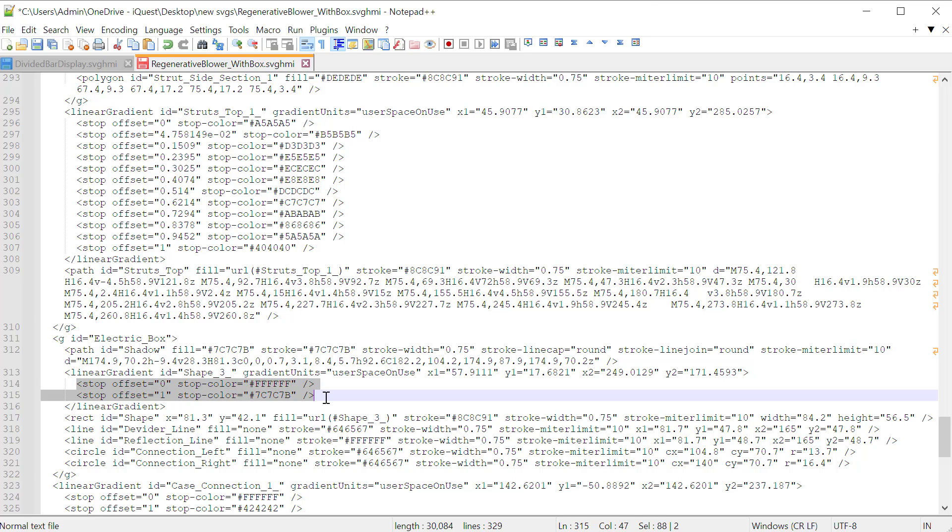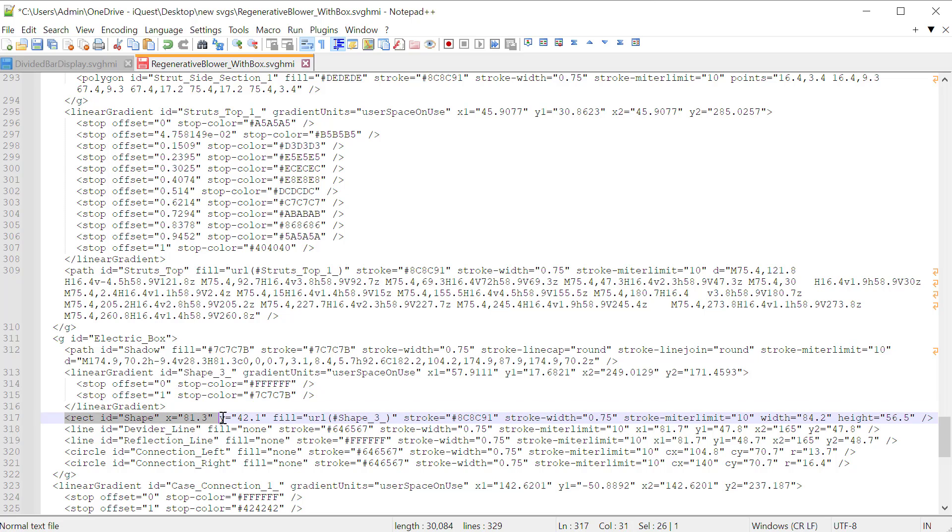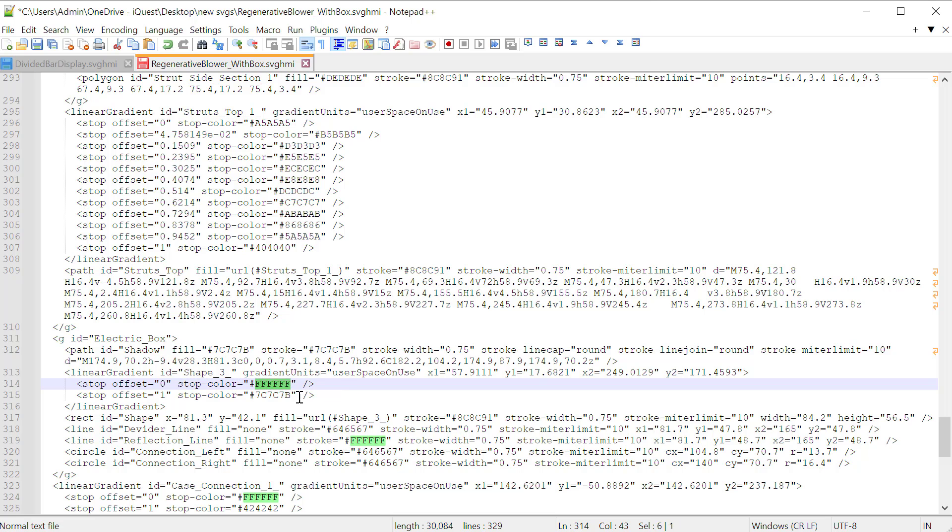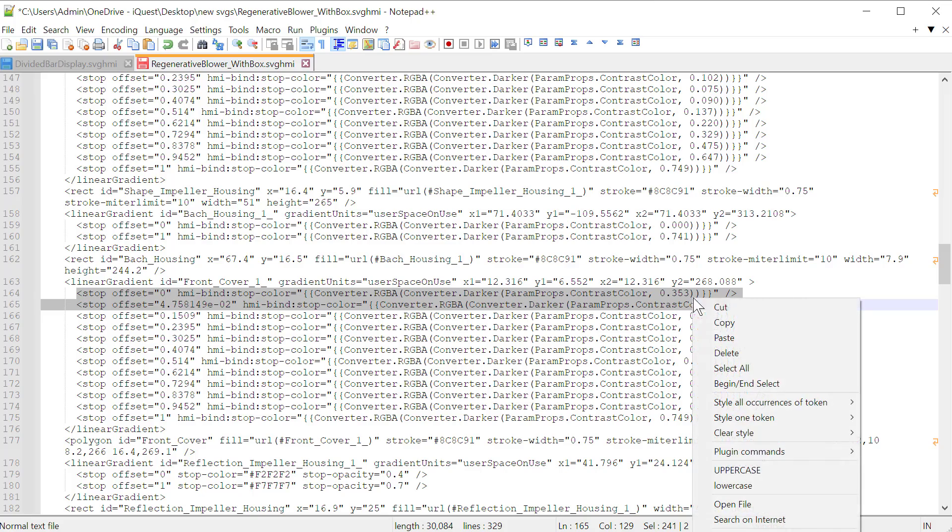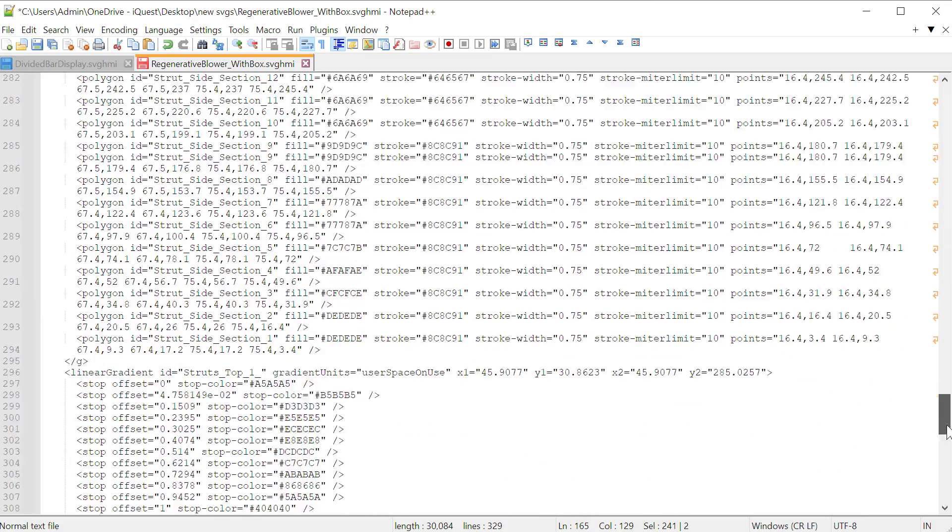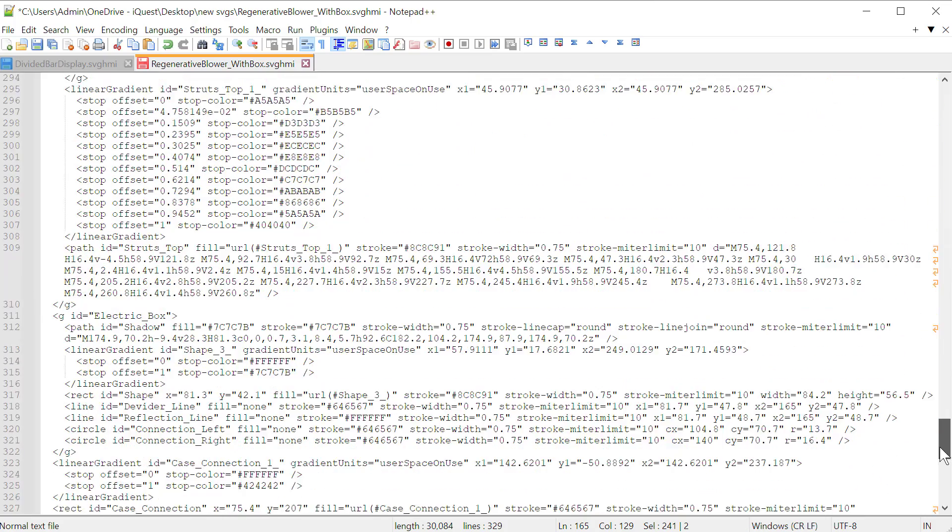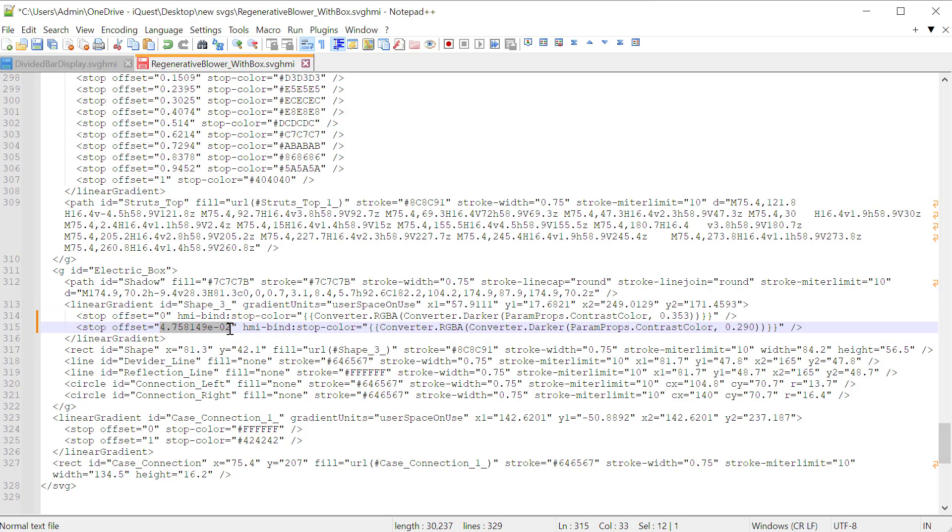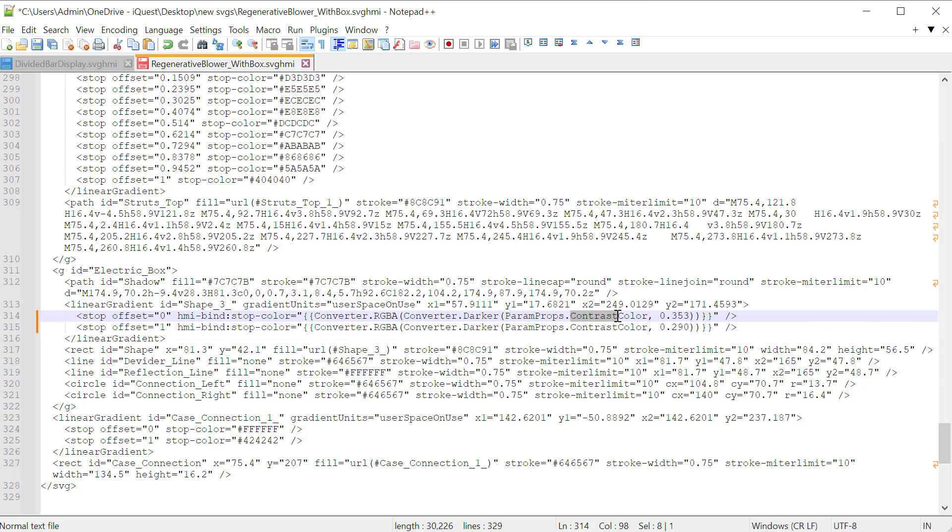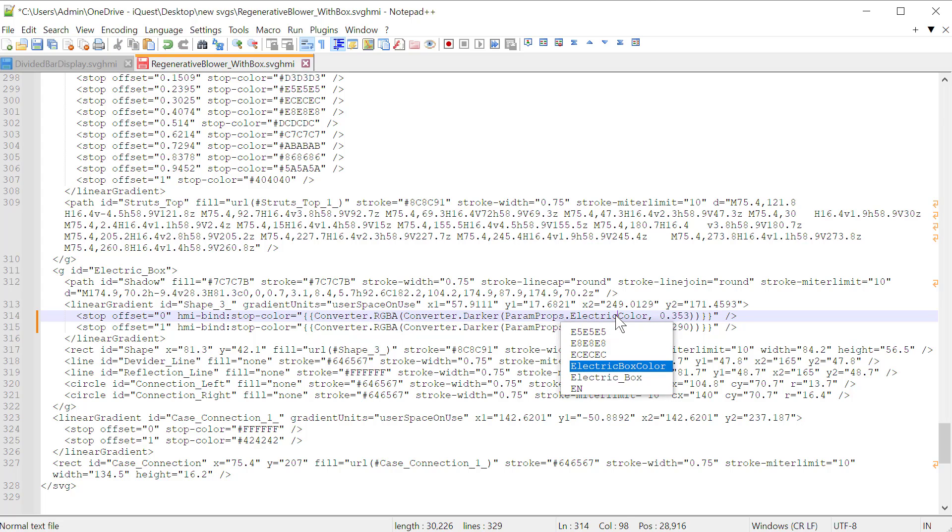So what we have to do is we have to use that property and set this electric box. And this is the color that it is. It's using a gradient. And so you can see the gradient just defines the color. And then here we are defining the shape. And it's using the URL function to take this gradient named shape 3 to give it its color. But the color is just hard-coded here. So what we need to do is go copy a couple of HMI bind directives from another place and pop them in here. And it doesn't really matter which one that I have. We're just going to go from 0 to 1. So I can just copy these two lines here and come back down to my electric box.